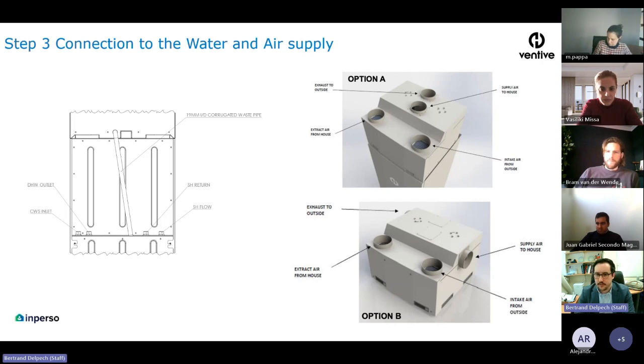A few more information as well about the installation process. Here you can see the back of the system, where you have the different inlets and outlets related to the district hot water, the radiator, or the water mains supply. Normally those will be labeled on the system, so you shouldn't make any mistake. Just double check that this is properly installed, as if it's not properly installed, it could cause damage to the heat pump.